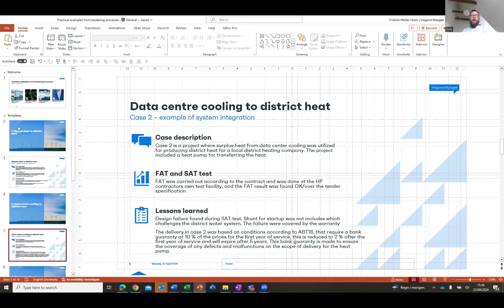Another example is a case where process cooling was made for district heating. The conflict was that an issue occurred due to fouling of the heat exchanger, because we were using a cooling tower with some dirty water present. Even though a filtration system was integrated, this still caused fouling problems, which affected the coefficient of performance.